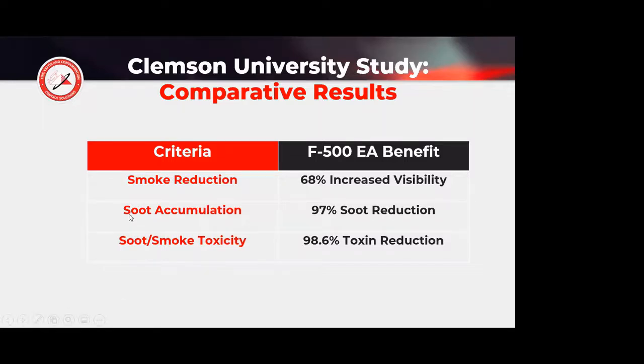The smoke accumulation on the plenum was reduced by 97%, which is quite amazing. That's a function of two things. The first one being we're interrupting the free radical to minimize the soot and smoke production. And the second one, we're actually encapsulating the unburnt carbon or hydrocarbon materials so that they can't form in the atmosphere.